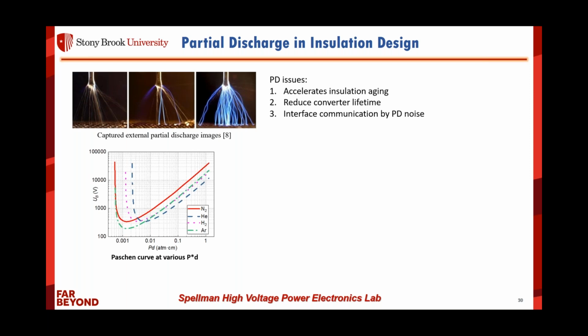It's totally different if you test this at ground level versus at higher altitude, because at higher altitude you have lower pressure. So at ground level, your breakdown voltage is probably somewhere here, but if you keep depressurizing the system, your breakdown voltage actually reduces.